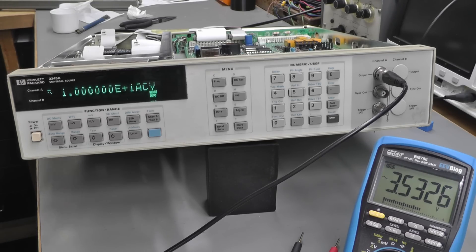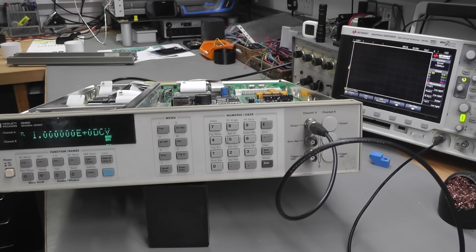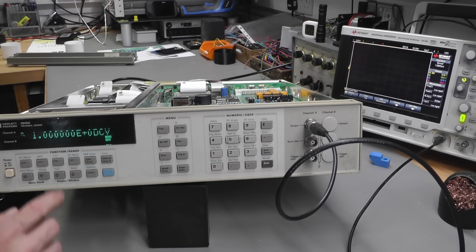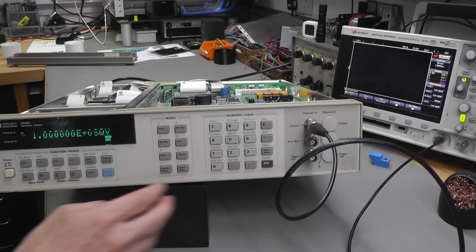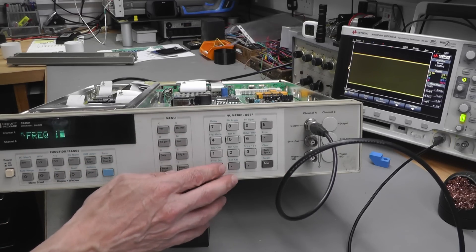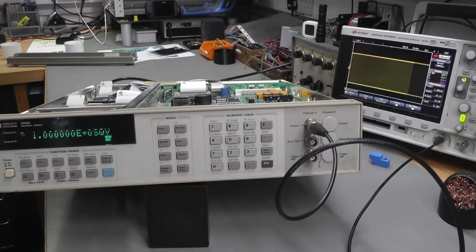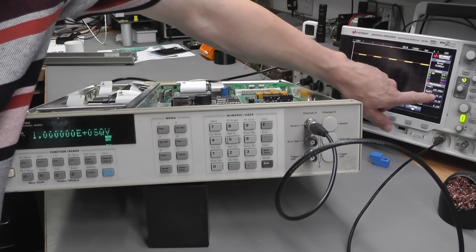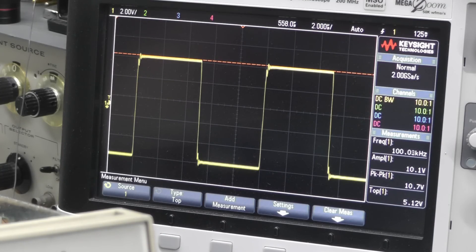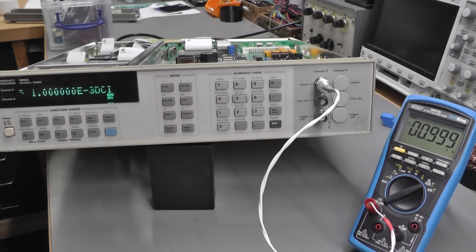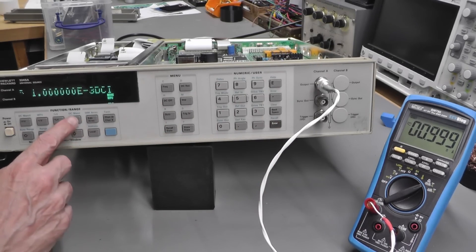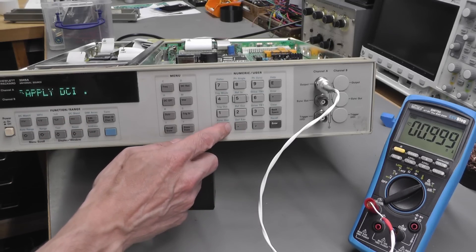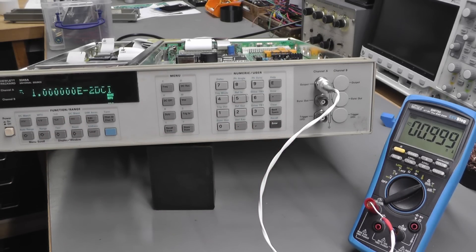Yep, 10 volts peak-to-peak, 3.53 RMS, perfect. Looks like it's calibrated. However, I will actually calibrate it myself against my 3458A and get it matched up to my other 3245A. How about testing some frequency outputs? Let me just set up the amplitude here and frequency—100 hertz over on the scope there. 100 kilohertz, that's working good. And the current output, well I've just sent 1 milliamp to it and that's perfect. 10 milliamp and 100 milliamp, perfect.